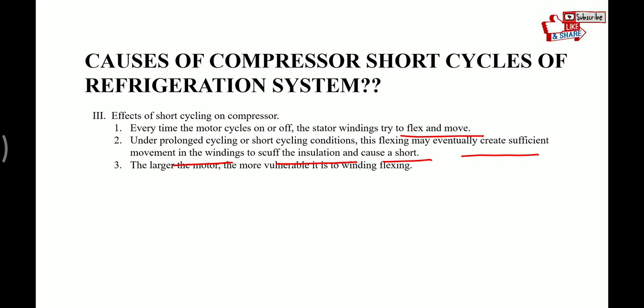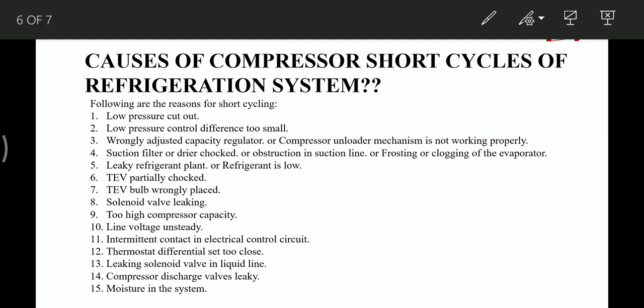There may be plenty of reasons. First is low pressure cutout switch is faulty. Second is low pressure controlled difference too small, meaning the on-off control difference in the pressure is very small. Then wrongly adjusted capacity regulator or compressor unloader mechanism is not working properly or is faulty.